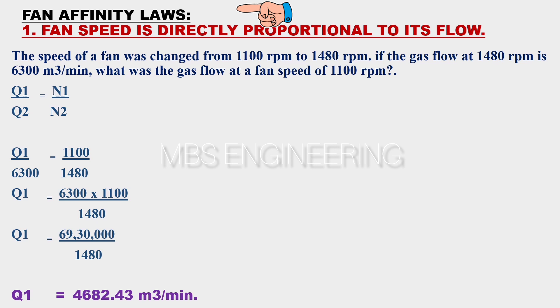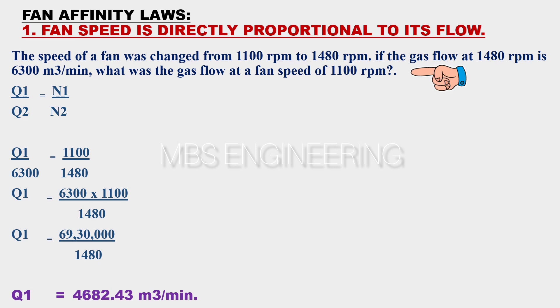Next, we learn the first affinity law and simple calculations. The first affinity law is: fan speed is directly proportional to its flow. Assume that the speed of a fan was changed from 1100 RPM to 1480 RPM. If the gas flow at 1480 RPM is 6300 cubic meters per minute, what was the gas flow at a fan speed of 1100 RPM? The fan speed N1 divided by N2 is directly proportional to its flow Q1 divided by Q2, where N1 and N2 are speeds in RPM.